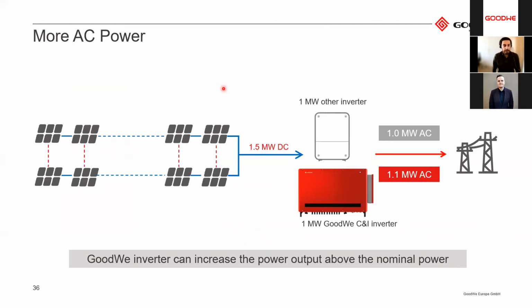For our C&I range, we also offer additional AC power. It's called AC overloading in some presentations. Basically, it means that the nominal or rated power of the inverter is maybe say 100 kilowatt, but then the maximum output power is 10% additional. So if you have an array that's a bit oversized, and another inverter brand is maybe sized to 1 megawatt, which is quite a high oversize, then that one would of course cap it at 1 megawatt, but ours would be able to output 1.1 megawatt instead.